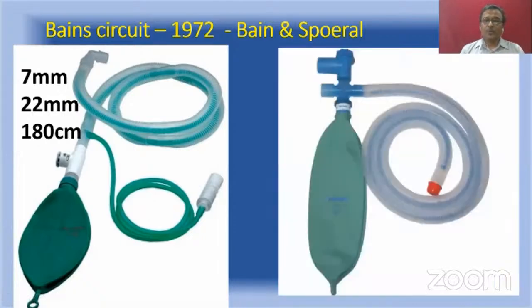Now I will show you a modified Bain circuit. What difference do you notice between these two? In the first one, the fresh gas attachment to the machine is far away from the circuit. There's a long tube between the connection and the circuit. But here, the circuit itself is mounted onto the anesthesia machine. So actually that is a disadvantage, because with the first circuit, you can move around. But here, since the reservoir bag is near the workstation, near the machine, you cannot move around, but there is a definite advantage.